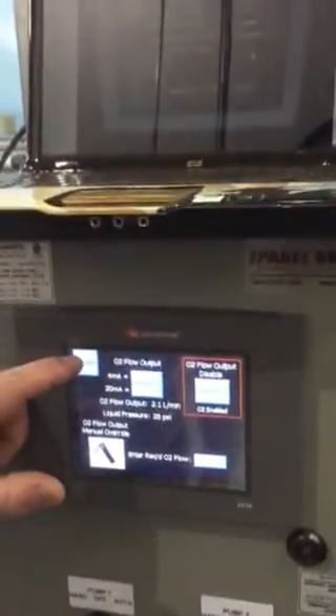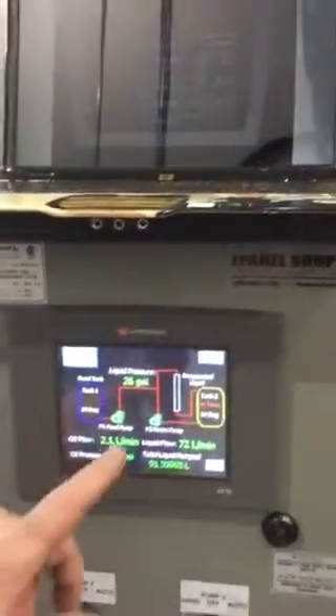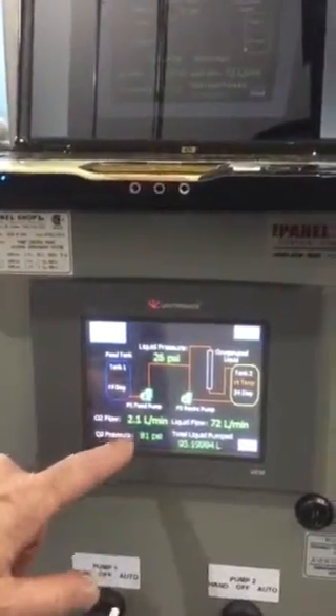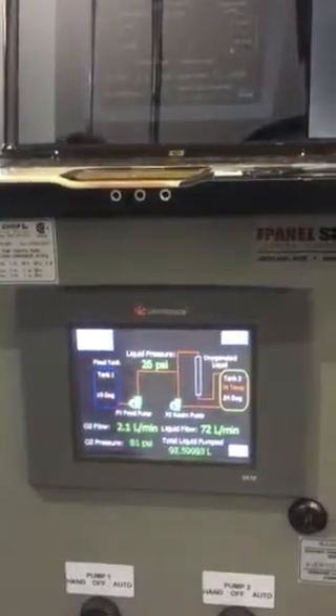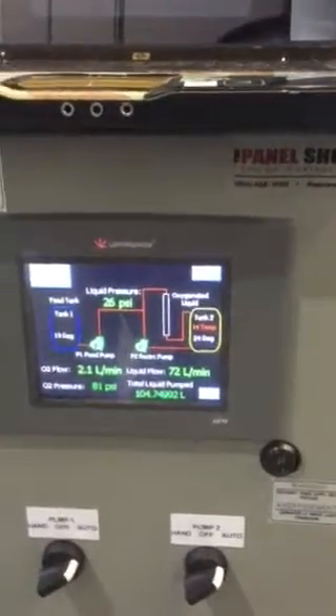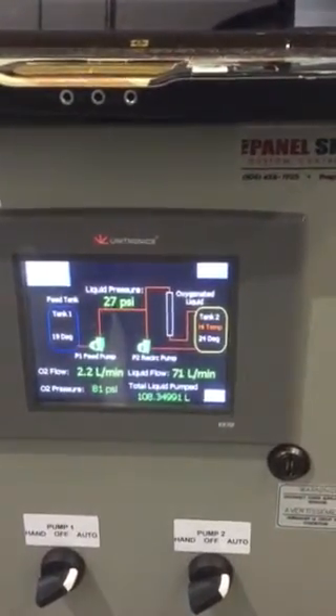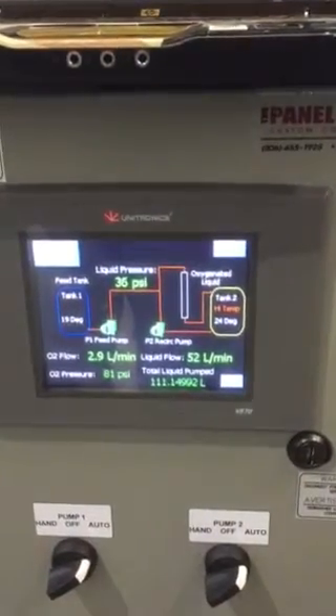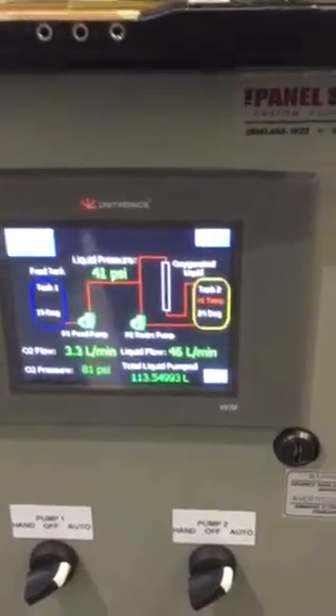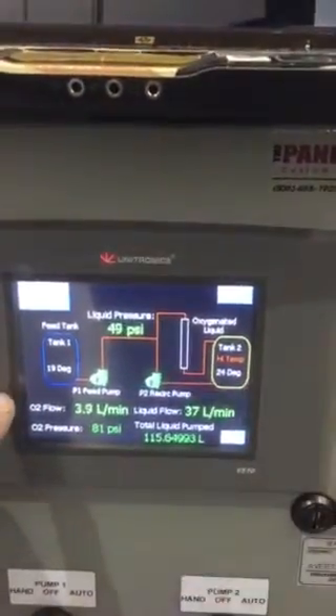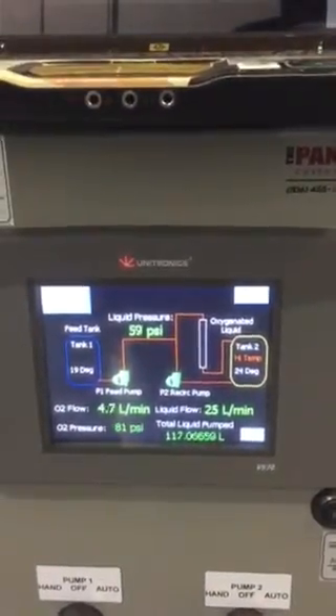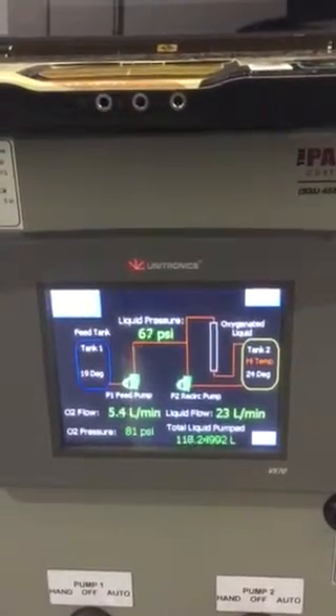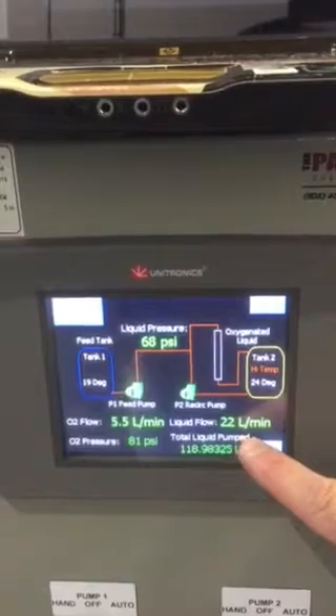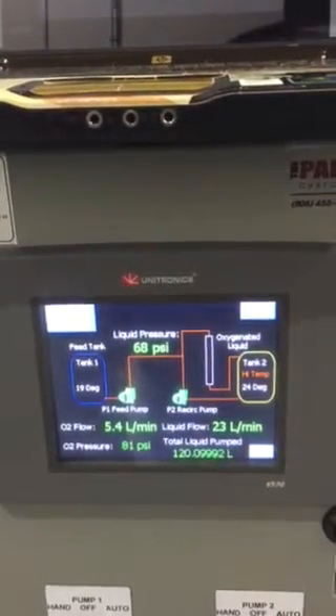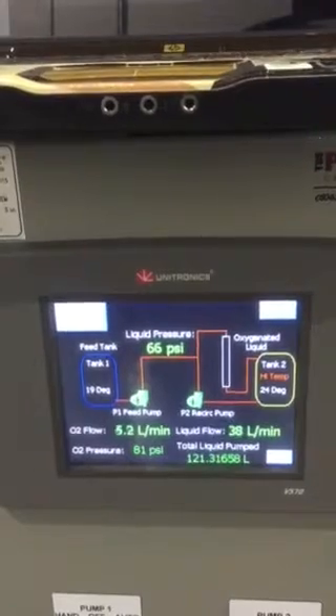We'll go back to the main menu screen just for a second, so I didn't do that before. So if you watch the liquid pressure and the oxygen flow, what I'm going to do is increase the back pressure. When I do that, you should see a large increase in oxygen flow. Now it's up. Oxygen flow rate, it's up to 4. Maximum flow at 5 on this, set for 5. As we get it up to higher pressure, you see you're down to 22 liters per minute on your flow rate. So it does follow automatically.